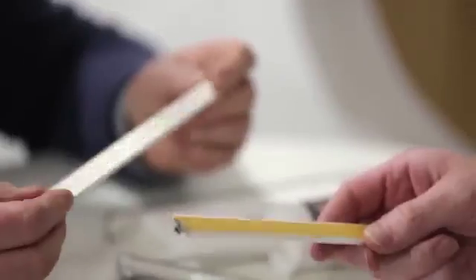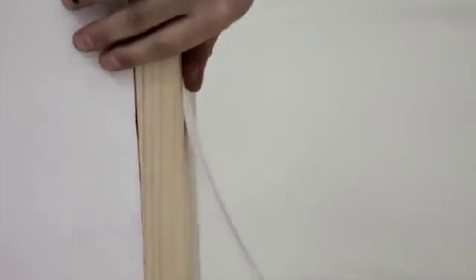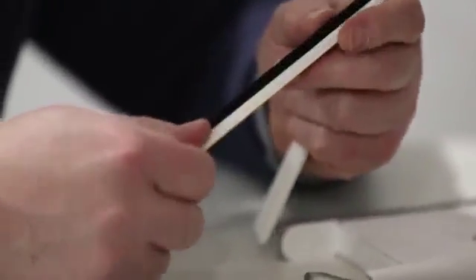I've noticed the grooves on them as well. Yeah, the grooves are there to take what are called intumescent strips. This one is a plain intumescent seal. The grooves are designed to take this, it's 15mm by 4mm, and they're there to expand if there is a fire and seal the door in its place. The alternative is the smoke seal; this one's a combined smoke and intumescent seal. All fire doors are governed by fire door regulations, and in certain regulations you need to have smoke seal protection.